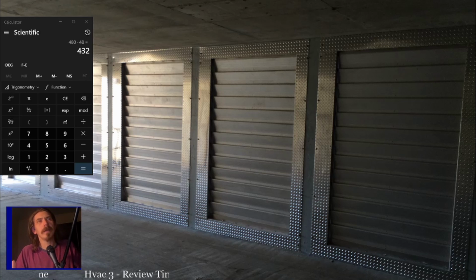All right. When you're checking the start relay, you want to test the amperage going through the circuit, and you'll see the amperage spike. And if that amperage spike doesn't drop within so much time, then there's an issue there. I think that's really the only way to check. Potential relays, generally, I see them failed open, failed closed. I can't think of a situation in which I needed to really pay attention to how long it's in the circuit, because so many newer ones have the backup. They have that backup time delay in them. So it's pretty rare that you see it for way too long. But yeah, so that's start relays and run capacitors, but we'll cover those a little more at some point.